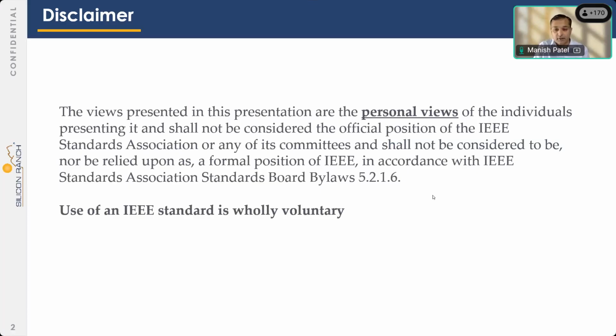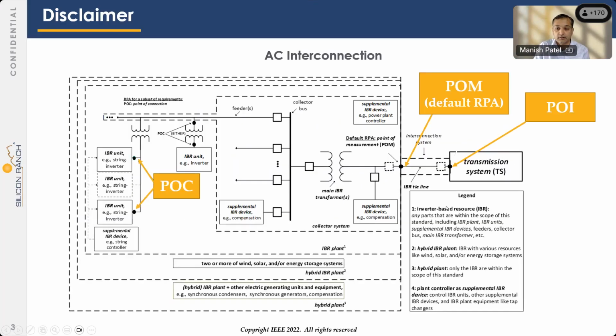I think Andy had this picture in his slide, but I think it's very important that we understand this. Most of the requirements of the standard apply at the point of measurement. That's the default reference point of applicability in the standard. This is, in simple words, the high side terminals of the main IBR transformer. Then there's a short tie line and then a point of interconnection. Very few requirements in the standard apply at the point of coupling. A few days ago, I thought only fault current injection requirements applied at the point of connection and directly on the terminals of the IBR unit. I think someone brought to my attention that there is something else in the standard that applies to the IBR unit, and that is something that we might want to clarify in the next revision, but we'll talk about that in a second.